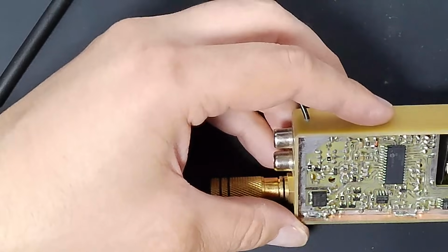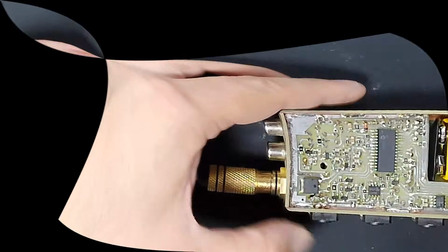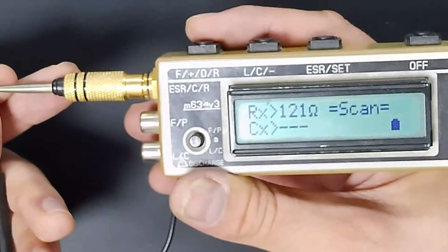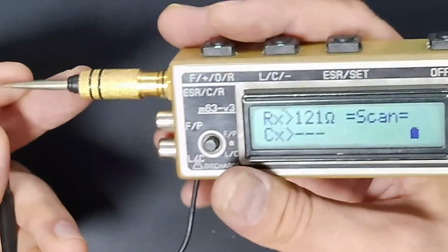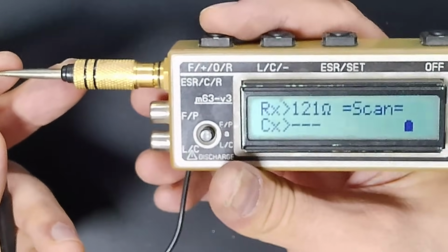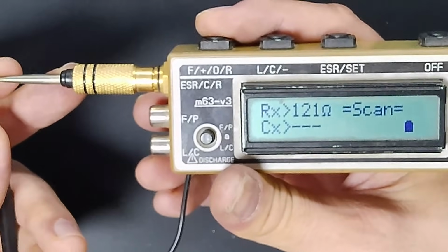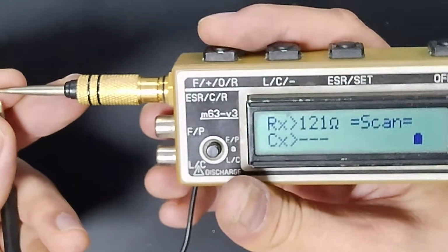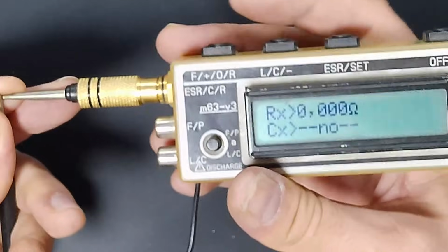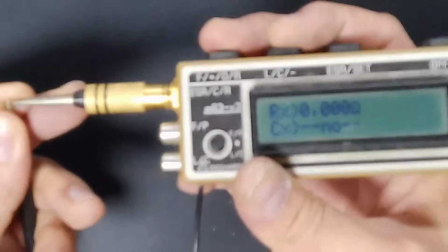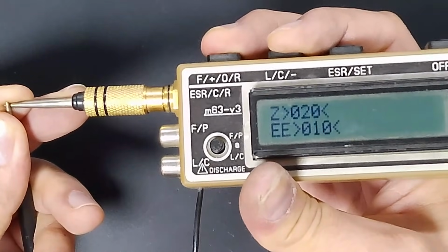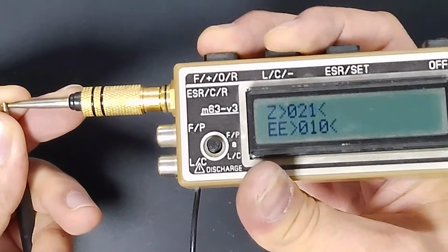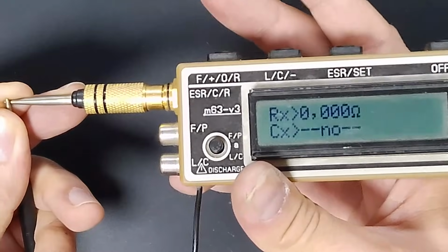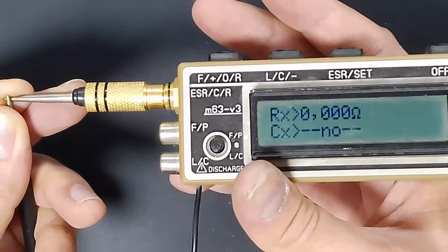So I can put this one back in its case. Let's try zeroing out these testing tips. First I need to set to constant resistance, small resistance testing, with this button. Then I need to short out the tips and press simultaneously the plus and minus buttons, and release them. Now it reads 0.